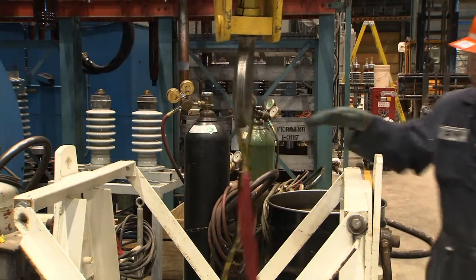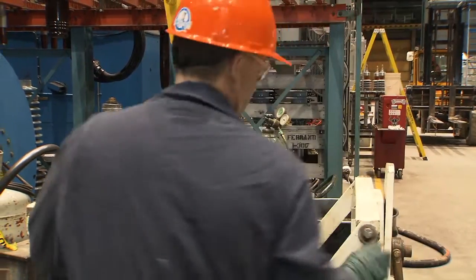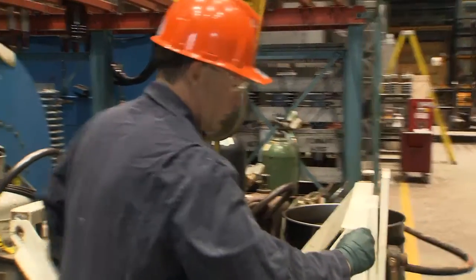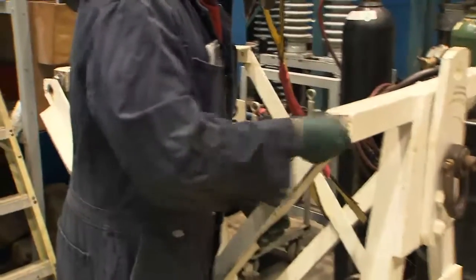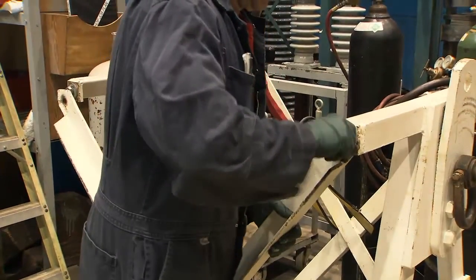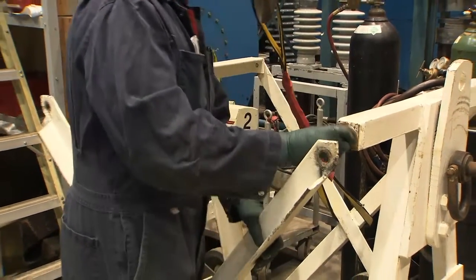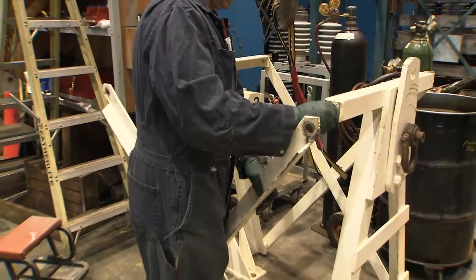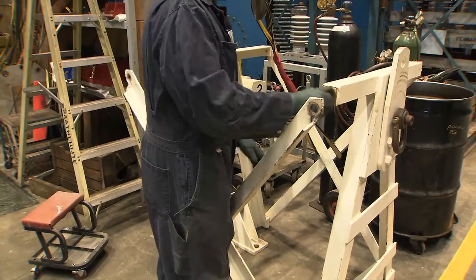Reconnecting the lifting jig to install the bushing onto the transport carrier. In order to connect the lifting jig to the bushing for placement in the transport carrier, begin by unscrewing each set of nuts and bolts connecting the crossmember to the lifting jig. Remove the crossmember and then loosely re-screw the nuts and bolts back into the lifting jig.